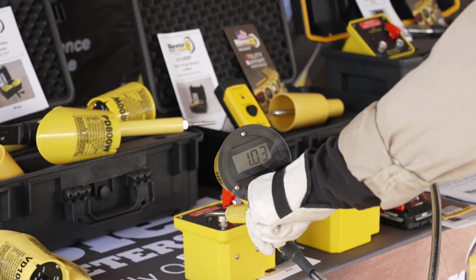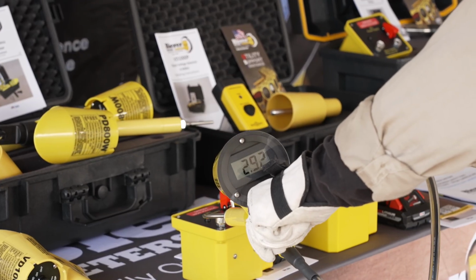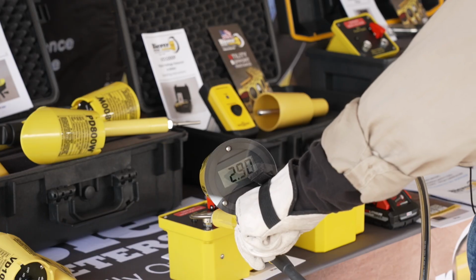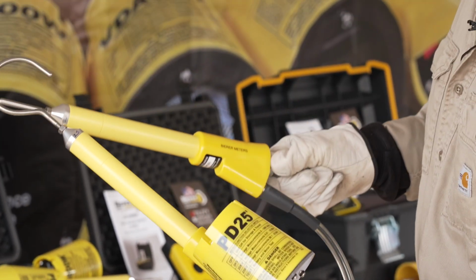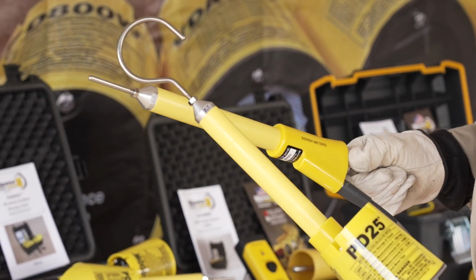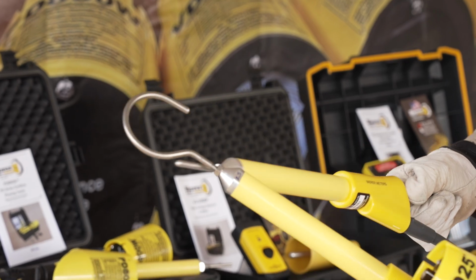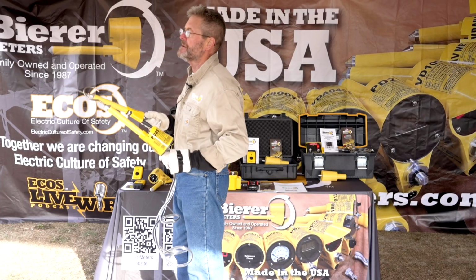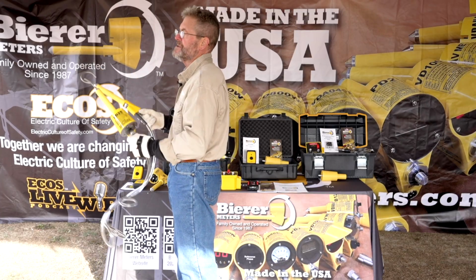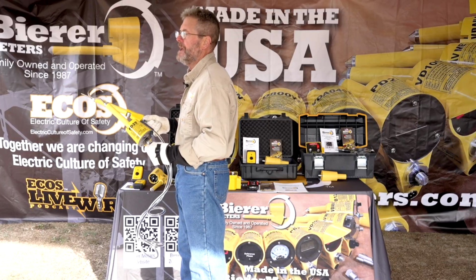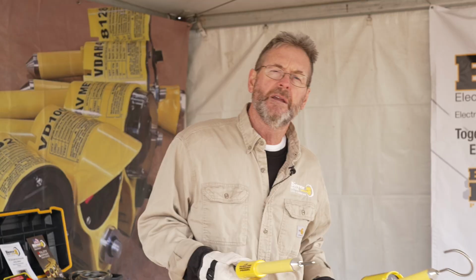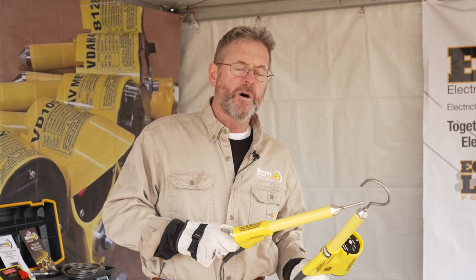So close to 3,000 volts. Notice how I'm testing using the accessories on the cone tip. Got a hook probe, and we have a straight probe. The reason why I test with accessories is because in just a moment, we're going to be using these tools on a hot phase. And when we use these tools, we always use the proper accessory. Do not just use cone tips.